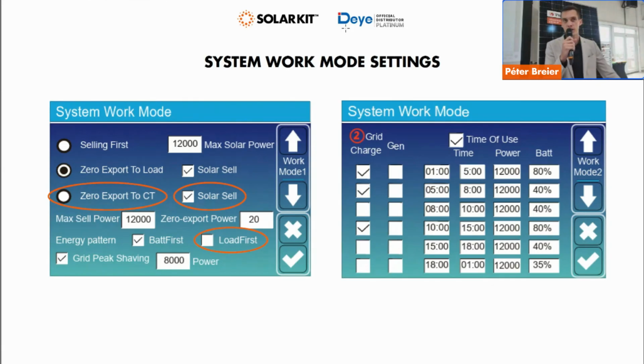This is the time of use mark. If you don't check the time of use, then the battery will not discharge any current until grid is connected. So you will not be able to use your batteries. There on the right side, there is also a percentage level. This would be the percentage level for that given time period until the batteries can discharge.